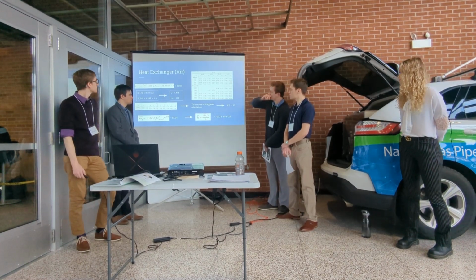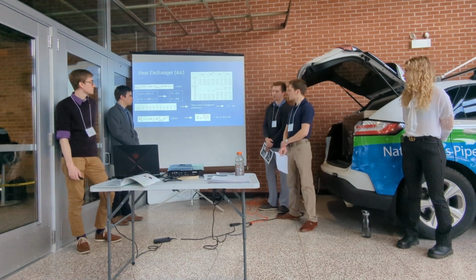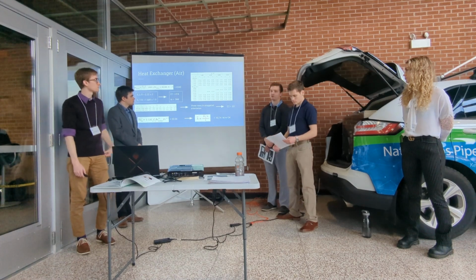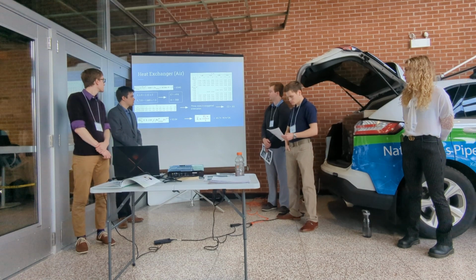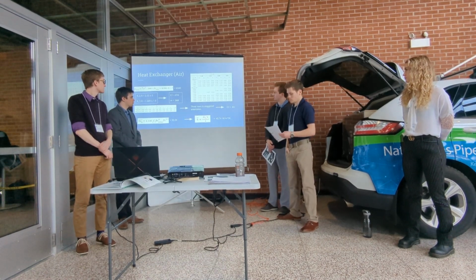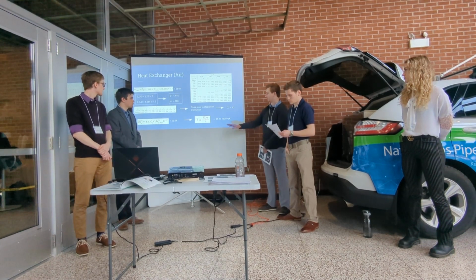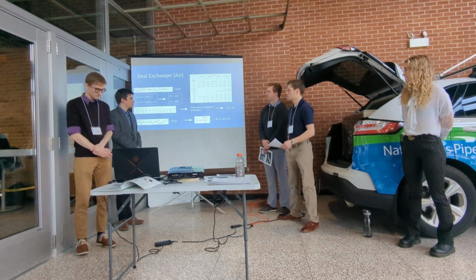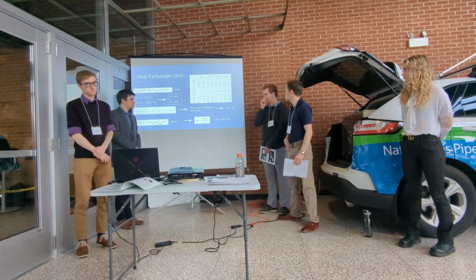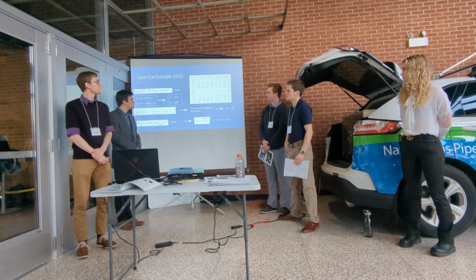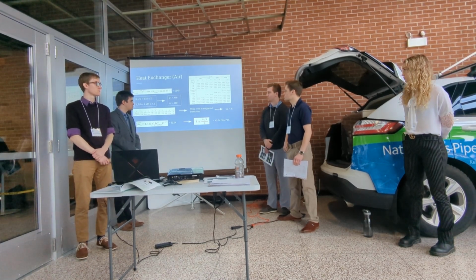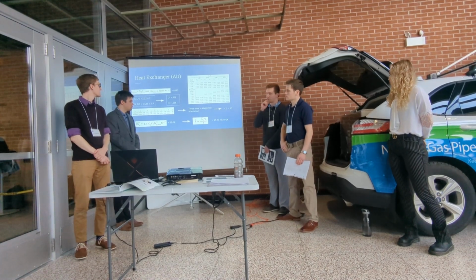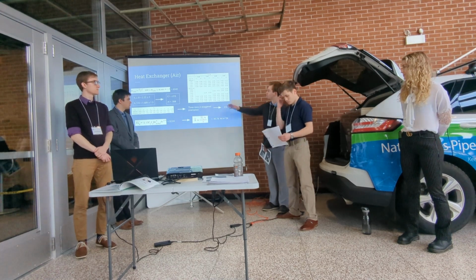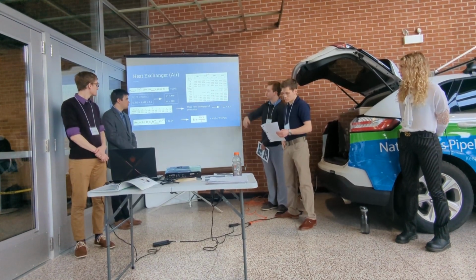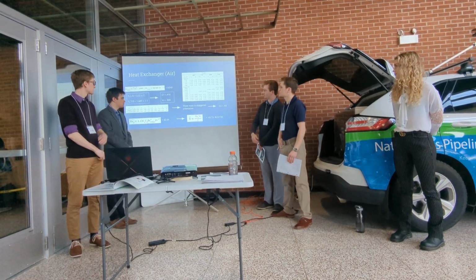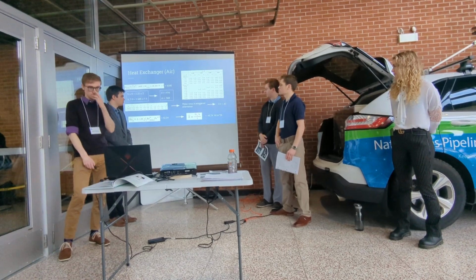So first we need to calculate the Reynolds number depending on the max velocity of the air crossing the heat exchanger. And so that is based on 3,000 CFM, which gave us a velocity of air of 10 meters per second, giving us a Reynolds number of 6,500. And then to calculate our Nusselt value, to calculate the convective coefficient, we need to determine the ratio of the length between each row and the diameter, and that gave us about 2.2, and we approximated to 2. And then we also had to take the ratio of the distance between each pipe in the row over the diameter, and that gave us approximately 1.5, giving us the constants from this table: C1 is 0.4, and then it's 0.568. And then since we wanted a staggered orientation with 3 rows, they gave us our final constant of 0.82.